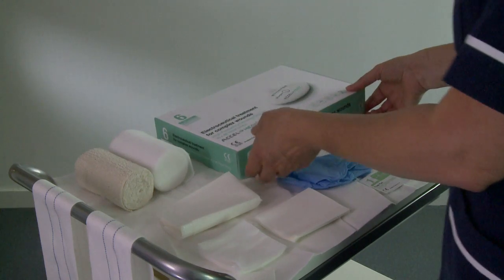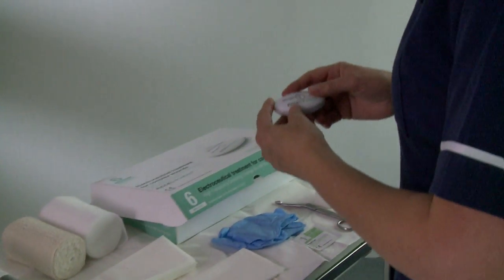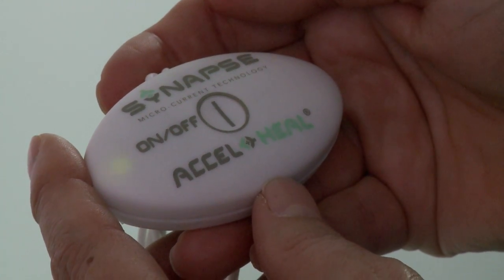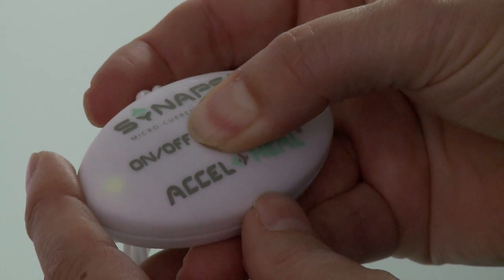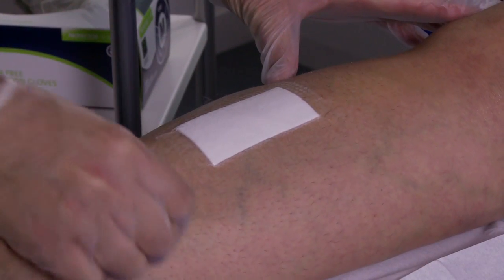Prior to proceeding, please test that the Accel-Heal treatment device is fully functional. Do this by holding the on-off button down for 2 seconds. A fast flashing green light will indicate that the unit is fully operational. Turn it off by holding down the on-off button for 2 seconds. It is important to apply Accel-Heal's electrode pads prior to applying any emollient.